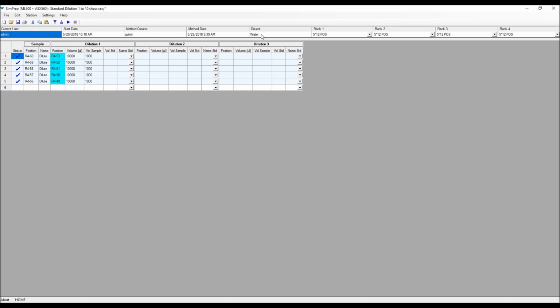Then your diluent, really that's just a reminder. It doesn't affect anything analytically speaking, but the diluent mark is there to make sure that your system diluent matches your sequence diluent. That way, if you have prep A that uses nitric acid as its diluent and prep B that uses just water or a mix of nitric and hydrochloric or something like that, then when you open up the sequence, you have to make sure that the diluent matches between the system and the sequence. It's just a reminder for the user that if they do need to change what's being used for the diluent, they take that extra step and remember to do it.